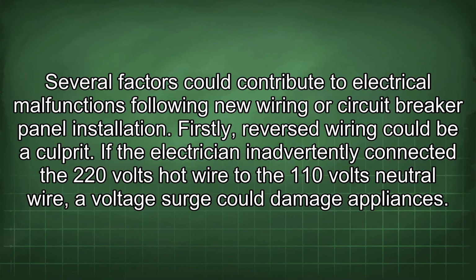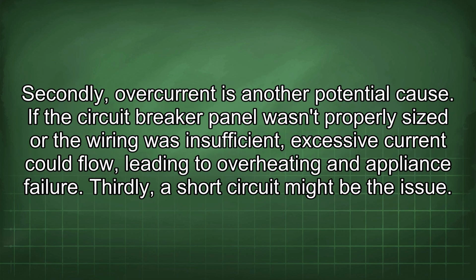Several factors could contribute to electrical malfunctions following new wiring or circuit breaker panel installation. Firstly, reversed wiring could be a culprit. If the electrician inadvertently connected the 220 volts hot wire to the 110 volts neutral wire, a voltage surge could damage appliances. Secondly, overcurrent is another potential cause.